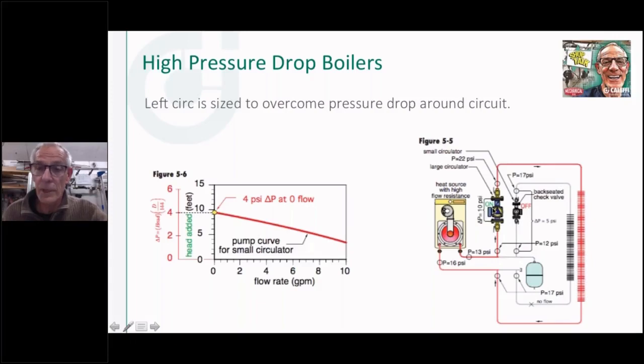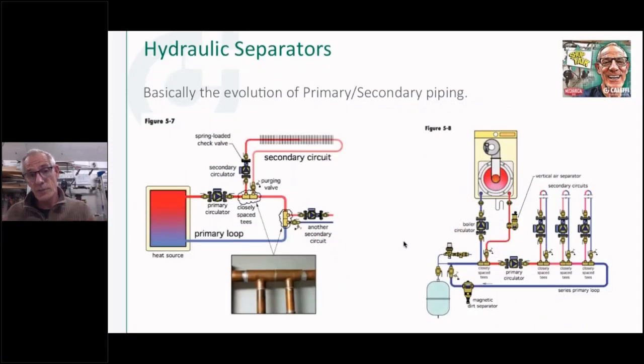Now, if the bigger one shuts off, you'll get some flow through that, but you might not have enough to overcome the pressure drop in this and get enough flow through that boiler that you don't start kicking it out on high limit, overheating that, and eventually you could end up with what I just showed on that previous picture, where you're going to overheat the heat exchanger in that boiler. You're not scrubbing that heat out of that heat exchanger with not enough flow going through it. So that's what we're going to get to with this primary secondary, where all these issues go away.